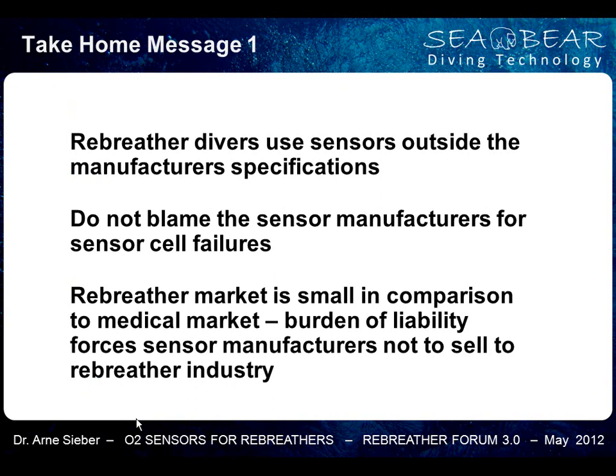So, here comes my first take-home message for today. Rebreathers use sensors outside manufacturers' specifications, and guys, don't blame the sensor manufacturers if the sensor fails. I mean, it's outside specifications. The rebreather market is so small in comparison to the medical market, and this burden of liability is actually what forces the sensor manufacturers not to sell to the rebreather industry anymore. If the divers come up and say, hey guys, my sensors don't work, so you are liable for that? Well, they are not, because you use them outside of the specifications.